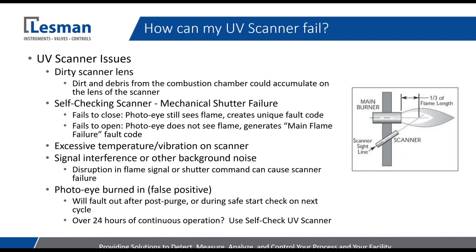Talking about UV scanners and how they can fail — the UV scanner is a lot more complex compared to the flame rod. A flame rod is a very simple rod, whereas a UV scanner has electricity, photo-eyes, and with self-checking UV scanners potentially mechanical shutters. You've got extra components that make up the scanner, which means there are different failure modes.